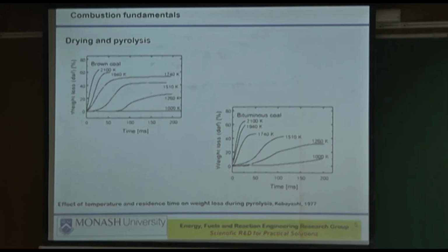In the same vein, the German brown coals, when they dry it, have about 6% ash, but they are slightly less reactive than ours. So they take a longer time to completely burn out, and therefore that's how their boilers are designed as well.